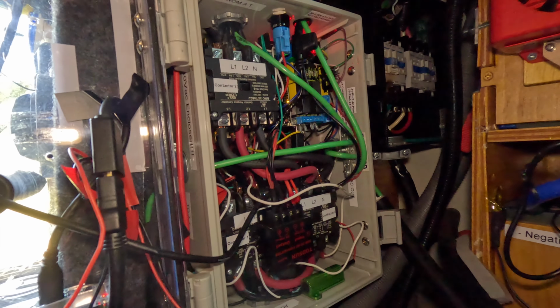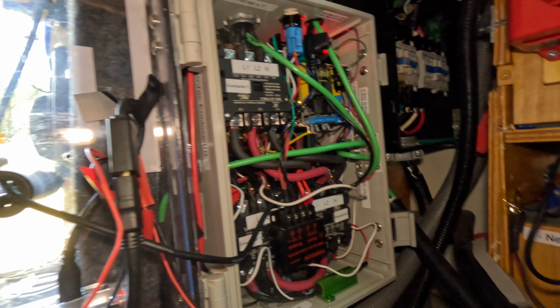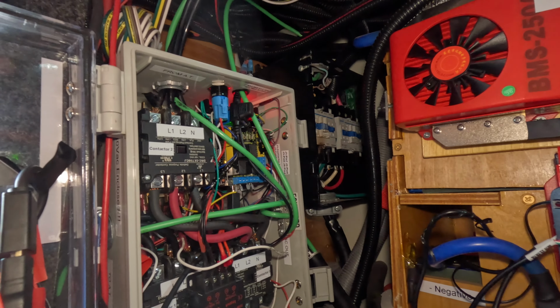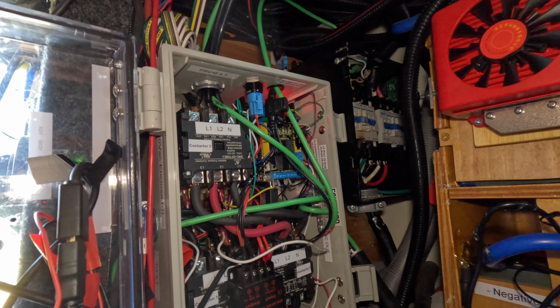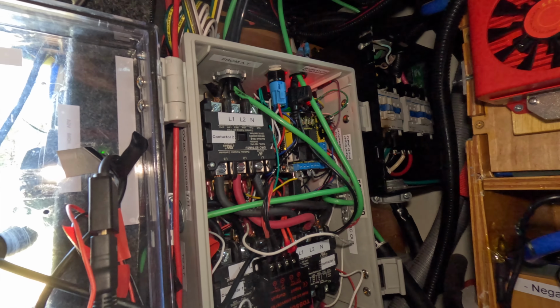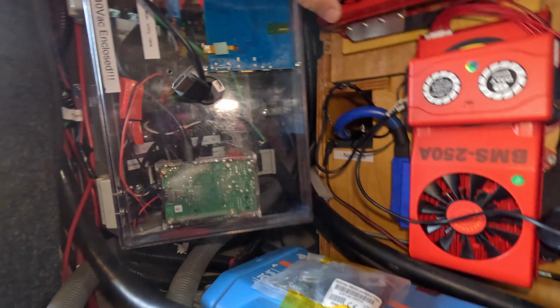And this, yes, is my secret weapon. I call it the voltage selector. What it does basically is when I have 240 volt coming in, it will just be a pass-through. It goes directly from this box and through a few contactors, feeds into two of those multipluses. And the interesting part is when I'm not having 240 voltage, meaning I only have one side of the leg, which is 120 volt, or I'm having the generator feeding the whole coach, I'll have the current directed from this box to the auto transformer that's in the back.